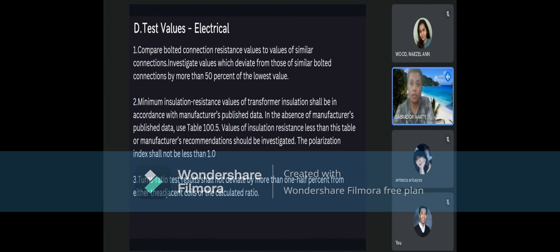Second, minimum insulation resistance values of a transformer. Insulation shall be in accordance with manufacturer's published data. In the absence of manufacturer's published data, use table 100.5. Values of insulation resistance less than this table or manufacturer's recommendation should be investigated. The polarization index shall not be less than 1.0.